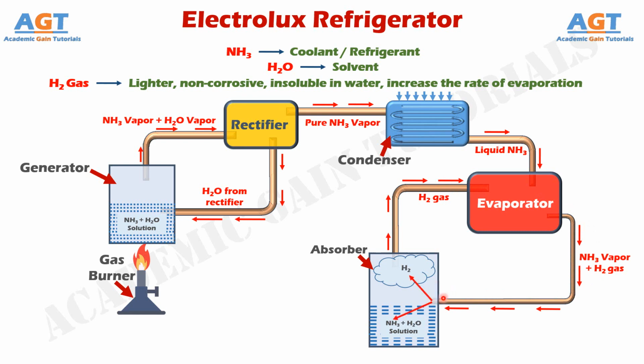Now, we already have water inside the absorber, and we know that ammonia is soluble in water, so the ammonia vapor gets mixed with water and forms an ammonia-water solution. But since hydrogen is insoluble in water, it will again go upwards, and from here it will again go into the evaporator, and mixing with liquid ammonia it will produce the refrigeration effect. Then again both ammonia vapor and hydrogen come to the absorber. Ammonia vapor forms a mixture with water, and hydrogen gets separated over here, and this goes on continuously.